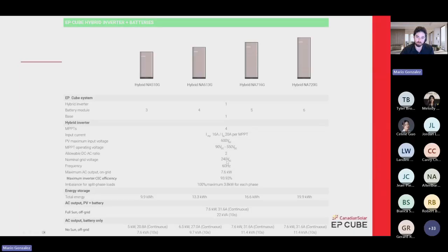Again, because we have the hybrid inverter, we can charge the batteries and feed your loads at the same time. It's a 240 volt, 120 system. The capacity is 7.6 kilowatt continuous for the inverter, but in backup, the 3 battery system goes down to 5 kilowatt, for the 4 to 6.5. Then 5 and 6 have the full 7.6 kilowatt continuous inverter capacity, and this is with no sun, basically. With full sun, all of the inverters will produce 7.6 kilowatt, because that's the size of the inverter. However, the inverter is limited by the battery amount when you're in backup mode or with no solar activity.